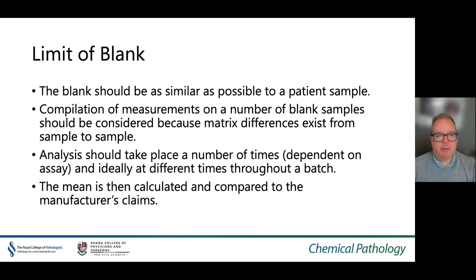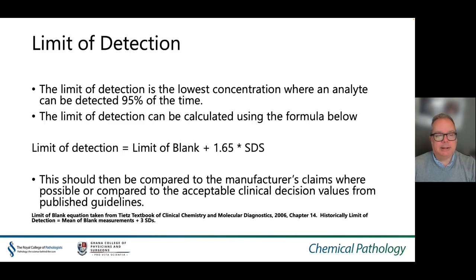Other experiments that may be performed but are not strictly necessary include the limit of blank. The blank should be as similar as possible to the patient sample — ideally a compilation of measurements on a number of blank samples, because matrix differences exist from sample to sample. Analysis should take place a number of times depending on the assay, ideally at different times throughout the batch. The mean is then calculated and compared to the manufacturer's claim. Extending this further, the limit of detection is the lowest concentration where an analyte can be detected 95% of the time, calculated using the indicated formula and compared to the manufacturer's claims or acceptable clinical decision values from published guidelines.